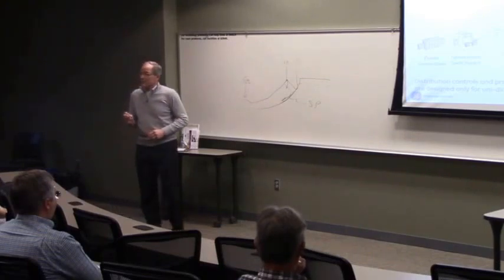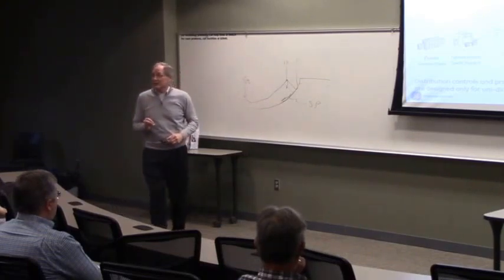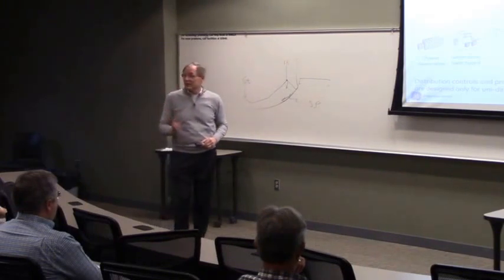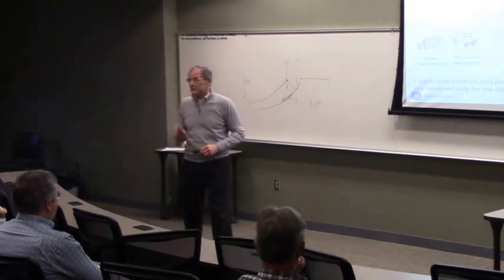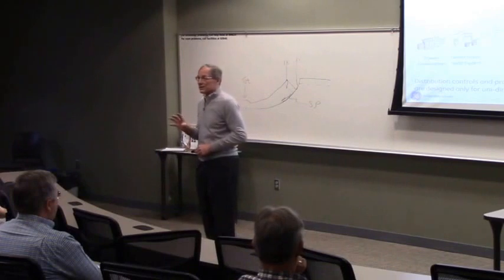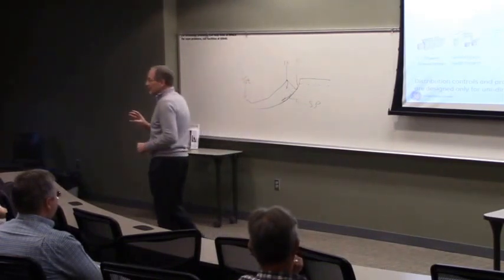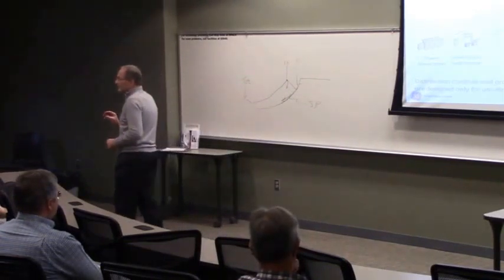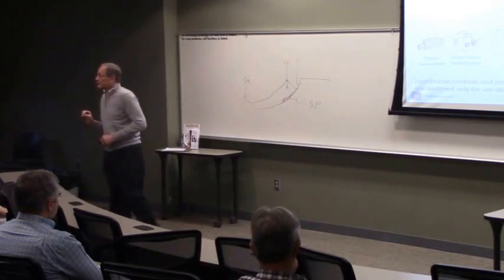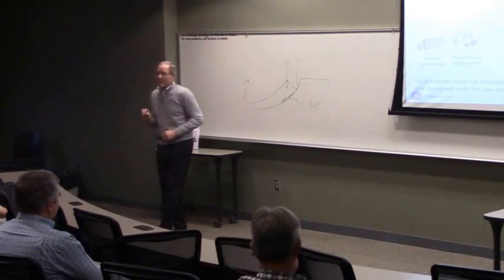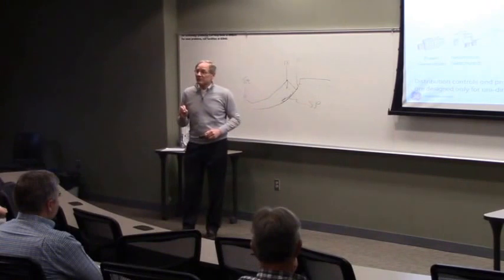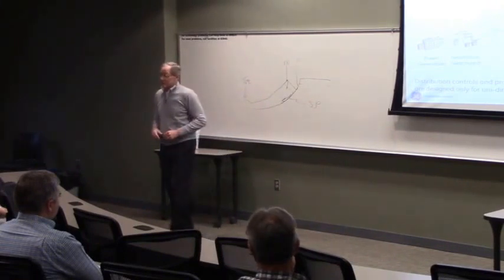But we used partial discharge acoustic monitors on the outside of the tank of the transformer in strategic places, and we could listen to the signature of the static electrification, and we could control that based on the temperature of the cooling liquid through the transformer. And we extended the life of this transformer that was failing by over a year.